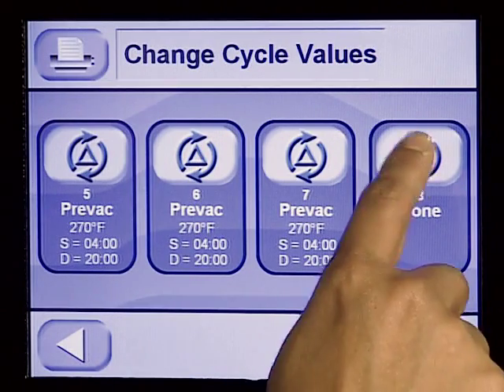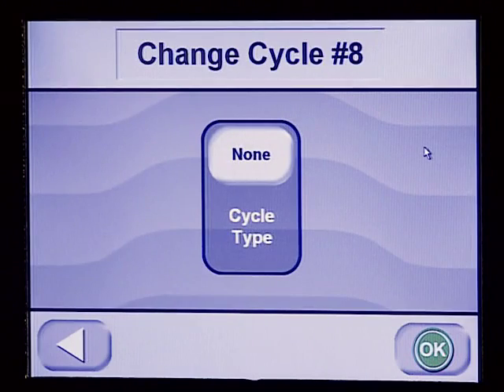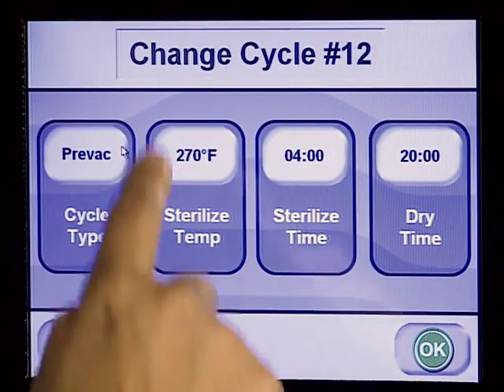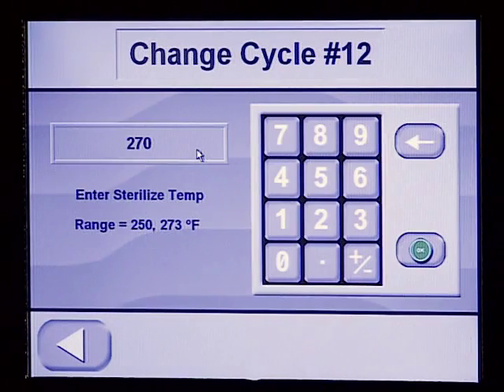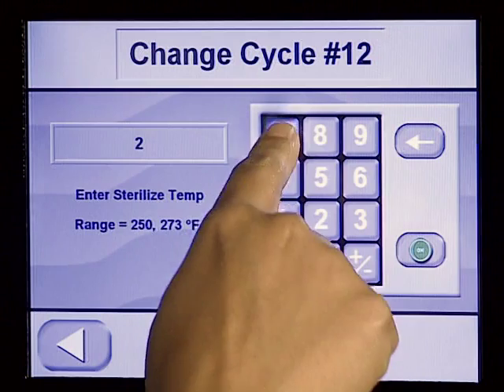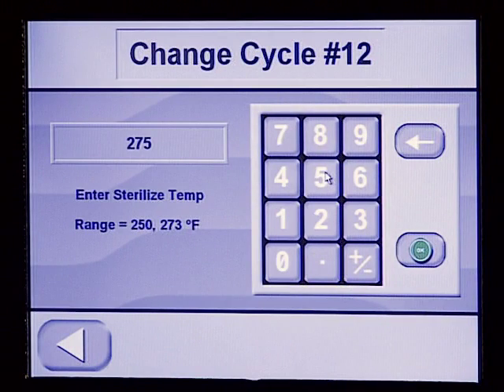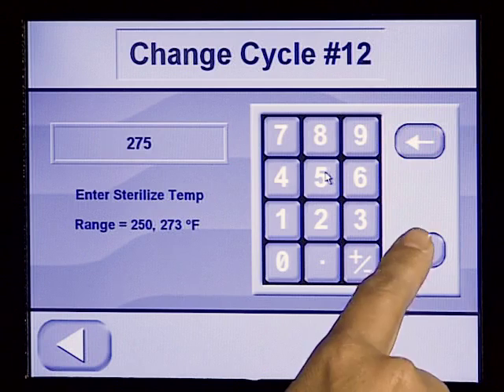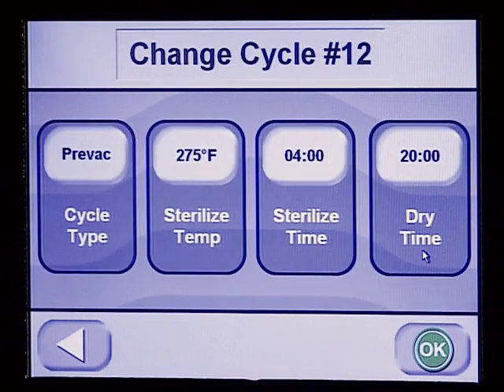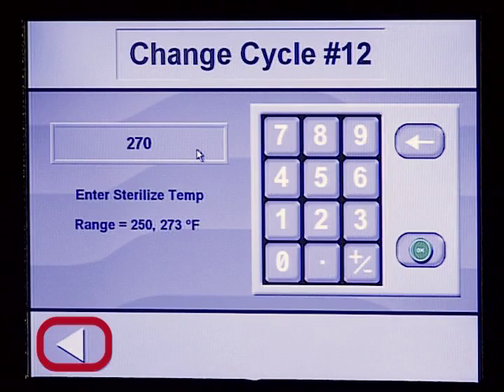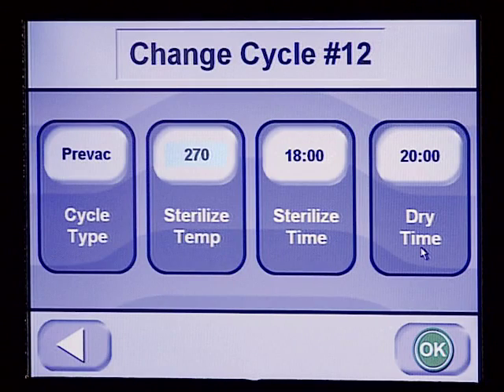Choose the cycle type. Then choose the cycle parameter you want to change. For example, to change the sterilize temp value for a pre-vac cycle, enter the desired temperature into the keypad, either 250 degrees Fahrenheit or ranging from 270 to 275 degrees Fahrenheit. If you make a mistake, use the backspace button on the keypad to erase what you've entered. Press the OK button to accept the new value, or press the Exit Screen button to keep the factory set cycle value and return to the Change Cycle screen.